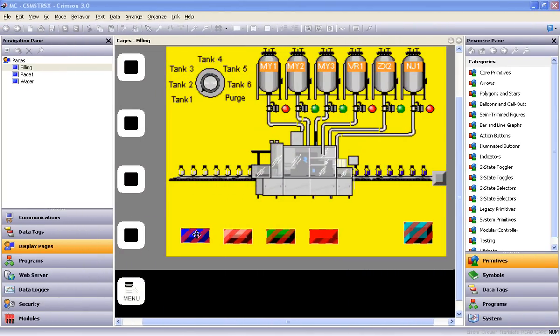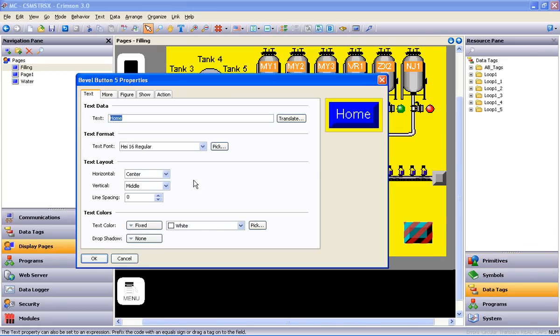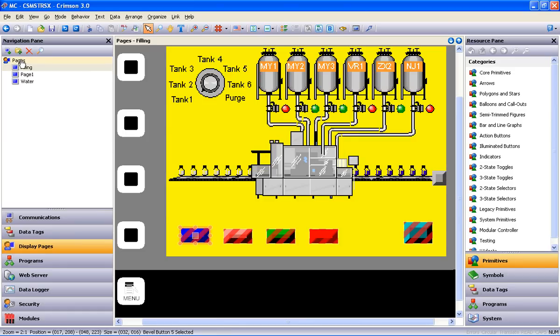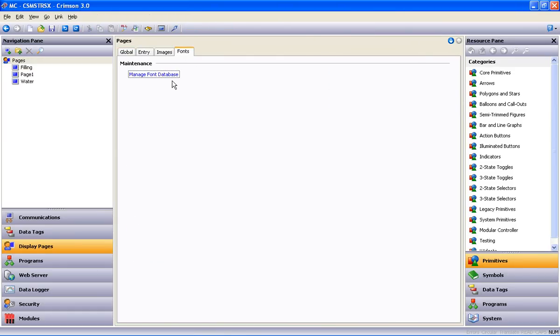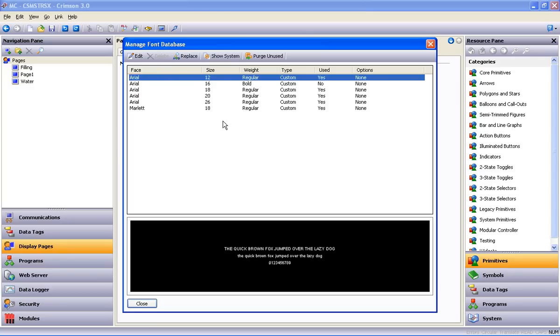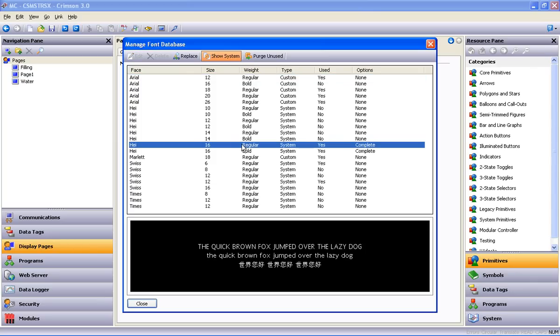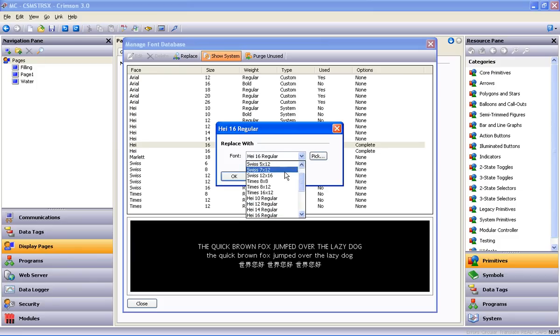When I try a resize on these navigation buttons, I soon figure out the font is just too big. So, I get a look at what font is being used, and then navigate to Crimson 3's Font Manager, a utility that allows you to swap one font for another throughout the database. Highlight Pages, select the Fonts tab, and then click on Manage Font Database. Since the font being used as a system or resident font, I click Show System to add the system fonts to the list. Select the one I want to replace, click Replace, select the font I want to replace it with, and say OK.